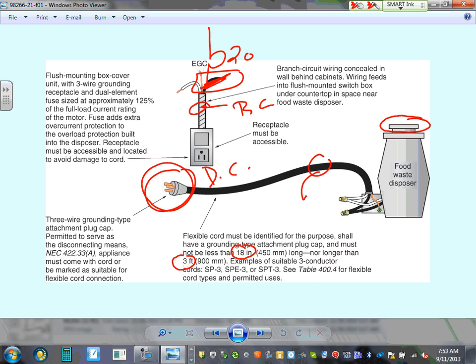You know, it comes with the appliances, but be aware that there is a limitation of minimum and maximum cord. You need 18 to 3 feet. Three feet is enough. So what's important for us, when you put your receptacles, make sure they are within 3 feet of where the appliance is going to be located. Then you're good to go. Any comments, guys? Any questions?